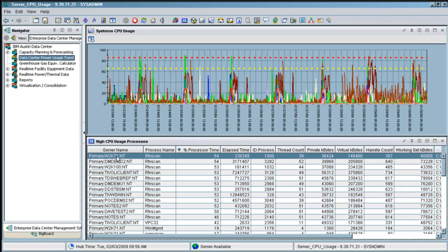It was driving 2% of incremental energy when it ran, which was a big deal given that our Austin data center was already running so close to full capacity. By staggering the virus scans, the team was able to reduce the peak loads on the servers and prevent costly power and cooling spikes.